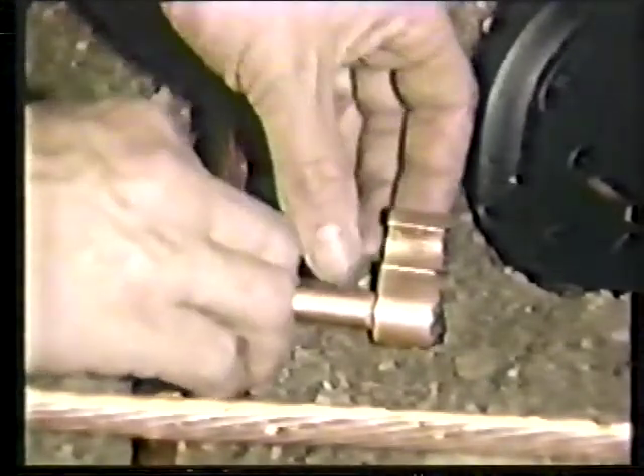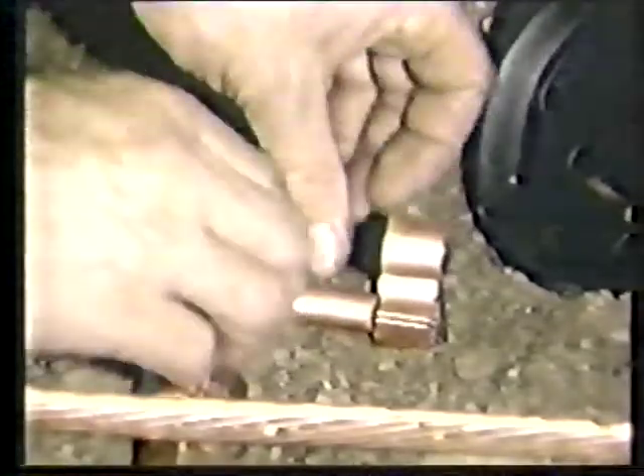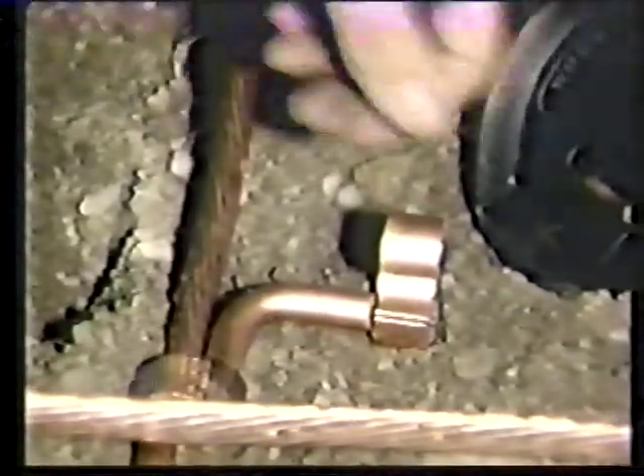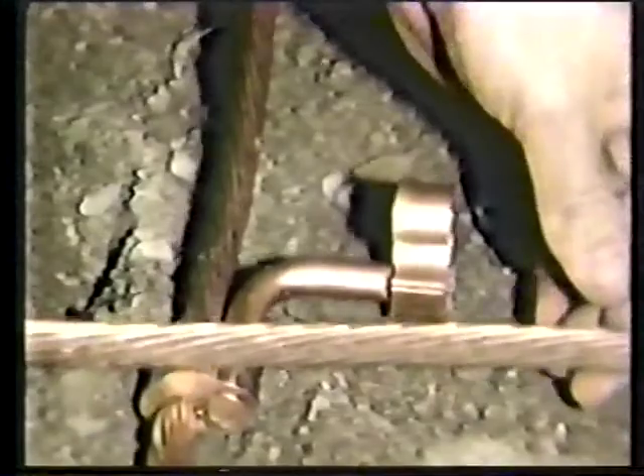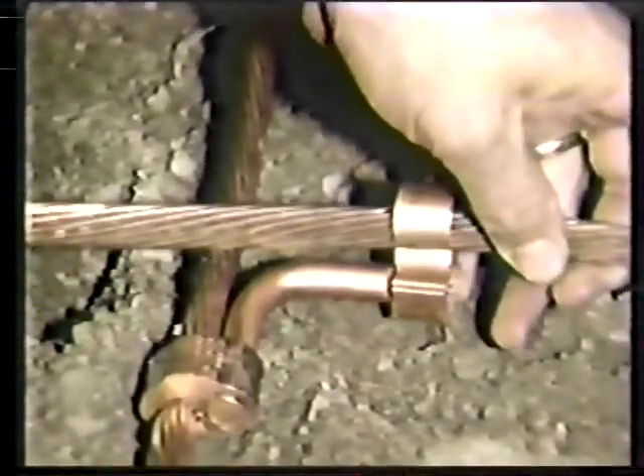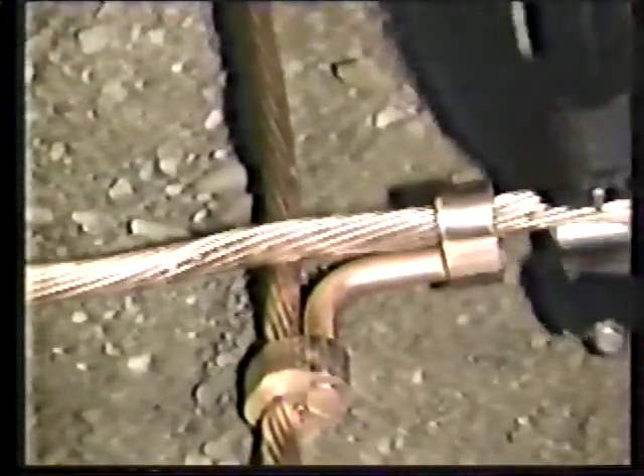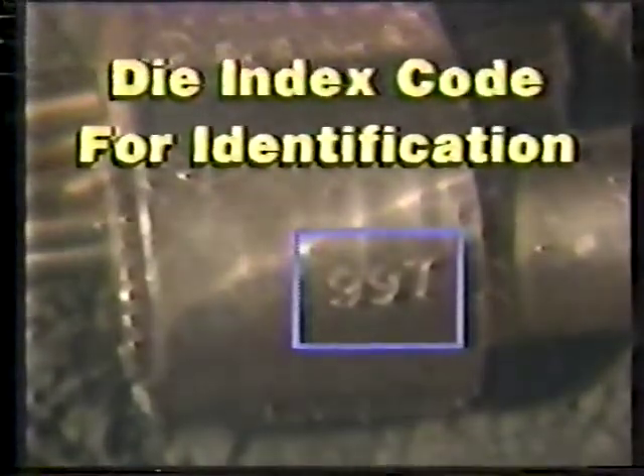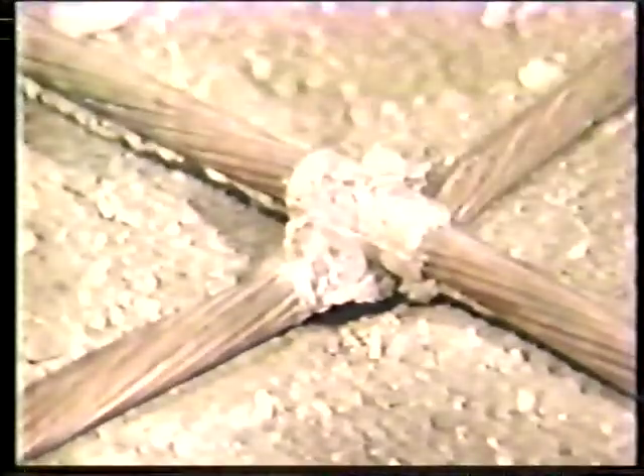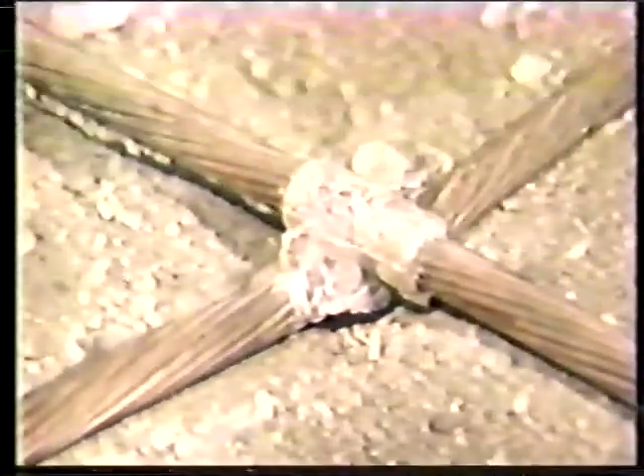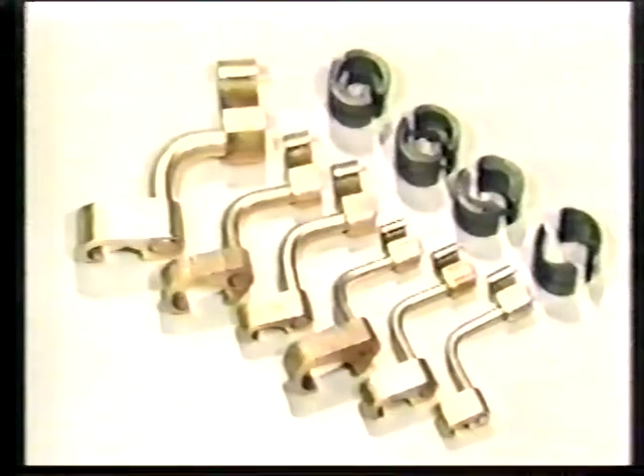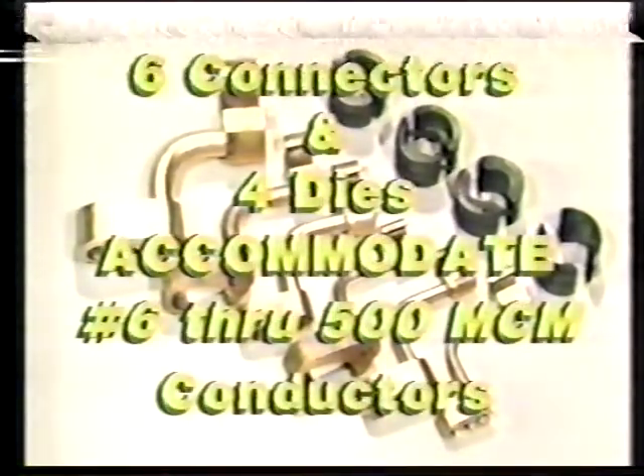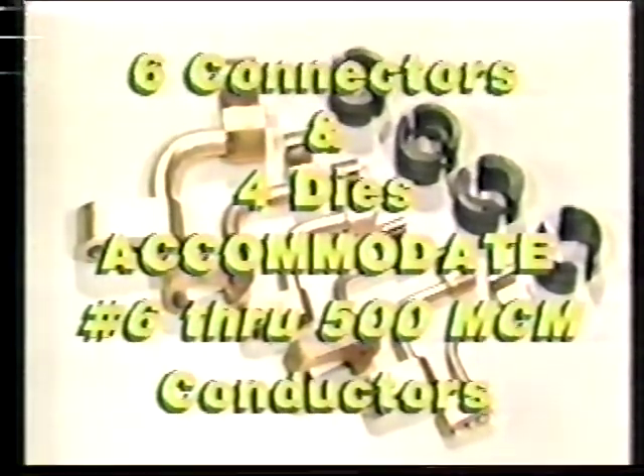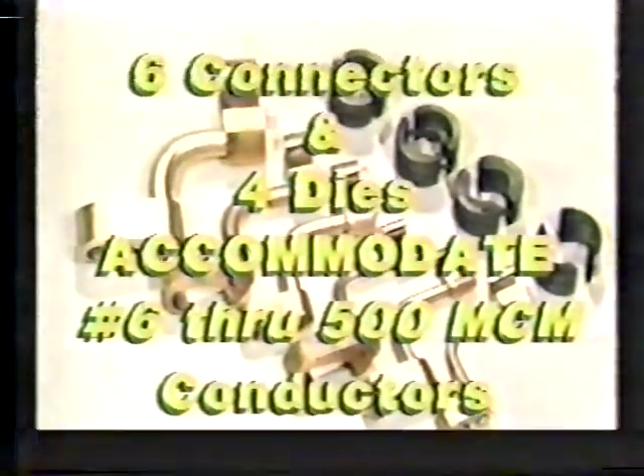This is simplified because the connector can be rotated to the proper position and will remain in place until crimped. For ease of inspection, a die index code is permanently embossed into the connector body. Inspecting an exothermic joint is not that straightforward. Because Burndy's Hygrid cross connectors are range-taking, only 6 connectors and 4 dies are required to accommodate conductors ranging from number 6 through 500 MCM.